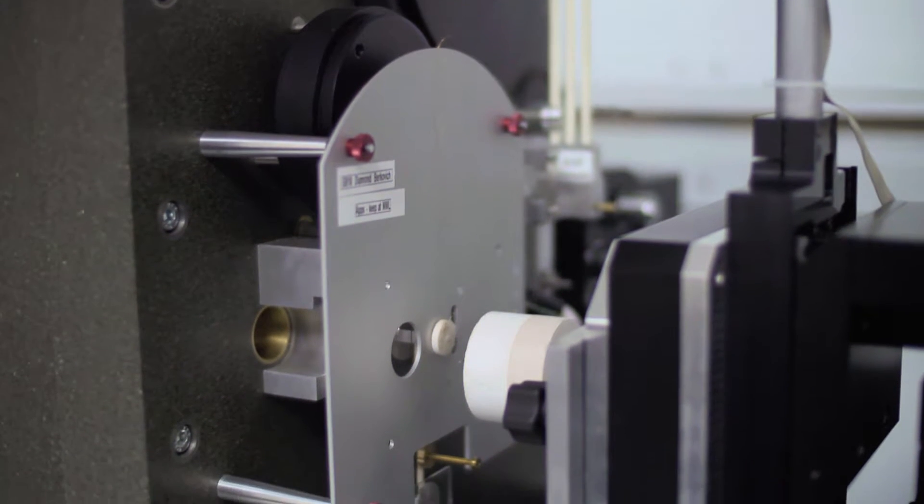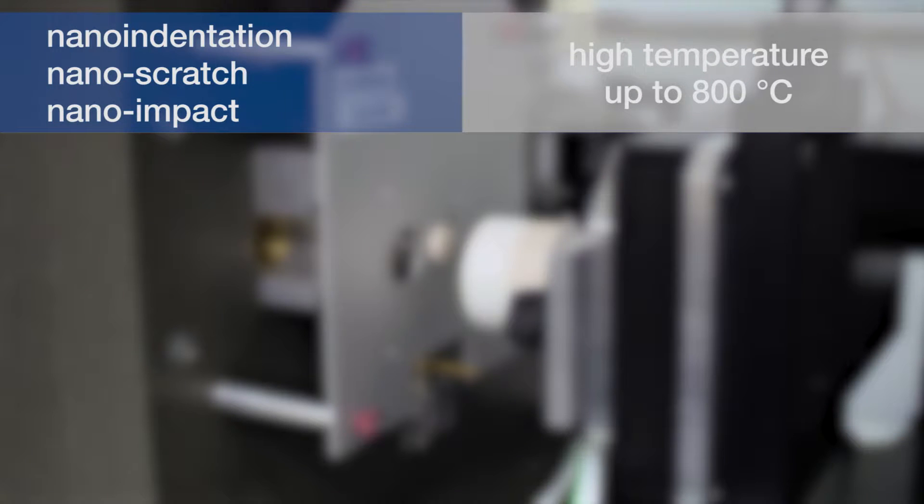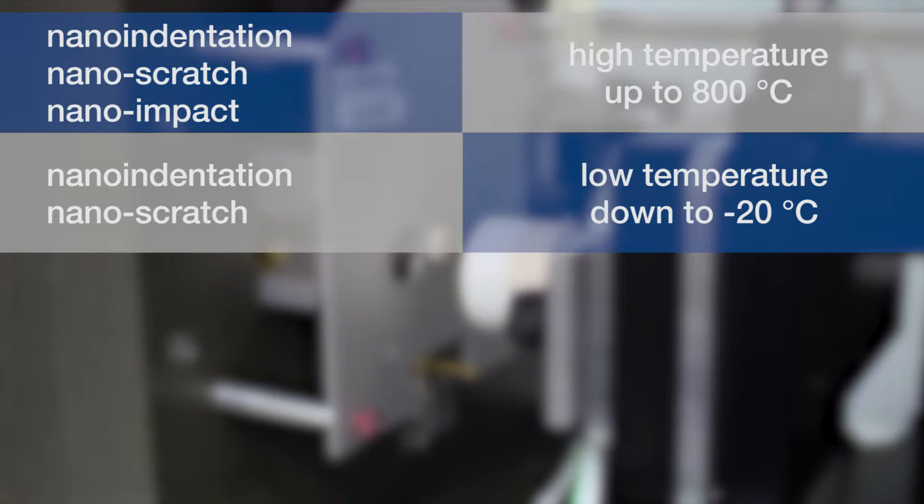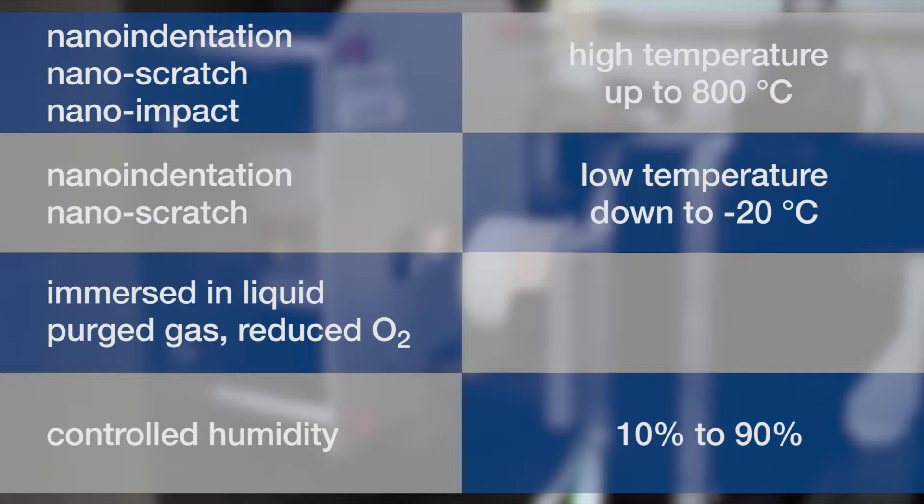High temperature nano-indentation, nano-scratch, and nano-impact to 800 degrees Celsius. Low temperature nano-indentation and nano-scratch to minus 20 degrees Celsius, with the sample and probe immersed in a liquid. In a purged gas-reduced oxygen environment, under controlled humidity levels from 10% to 90% relative humidity.